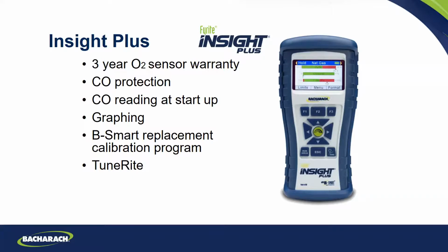You always want to wait till you get up to steady state efficiency, and it tries to get it to steady state efficient, which you look at by temperature. If something's out of whack for that 80% furnace, like it's showing on that screen where you're in the red, it's going to say you have a problem here. You hit it and it might tell you, you have too much CO. You ask, well what do I do, and it'll say look at these 4 things. It's not saying this is exactly what it is, but it gives you something to look at - maybe look at flame impingement, dirty burners, maybe you're overfired or underfired, whatever. So it's like a service assistant built in.